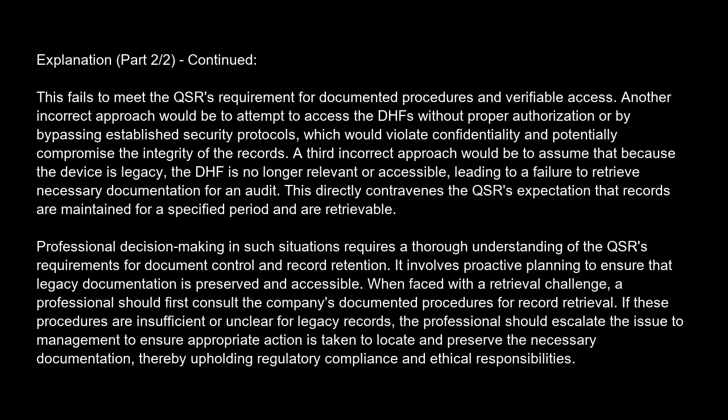A third incorrect approach would be to assume that because the device is legacy, the DHF is no longer relevant or accessible, leading to a failure to retrieve necessary documentation for an audit. This directly contravenes the QSR's expectation that records are maintained for a specified period and are retrievable.